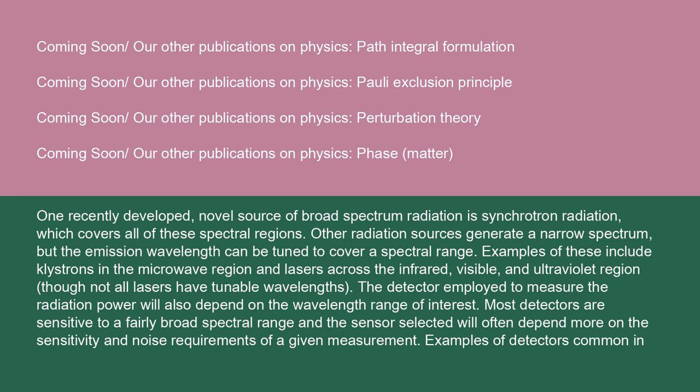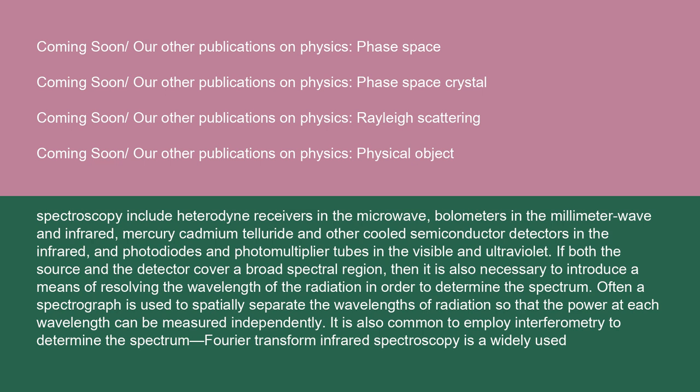The detector employed to measure the radiation power will also depend on the wavelength range of interest. Most detectors are sensitive to a fairly broad spectral range, and the sensor selected will often depend more on the sensitivity and noise requirements of a given measurement. Examples of detectors common in spectroscopy include heterodyne receivers in the microwave, bolometers in the millimeter wave and infrared, mercury cadmium telluride and other cooled semiconductor detectors in the infrared, and photodiodes and photomultiplier tubes in the visible and ultraviolet. If both the source and the detector cover a broad spectral region, then it is also necessary to introduce a means of resolving the wavelength of the radiation. Often a spectrograph is used to spatially separate the wavelengths so that the power at each wavelength can be measured independently. It is also common to employ interferometry to determine the spectrum.